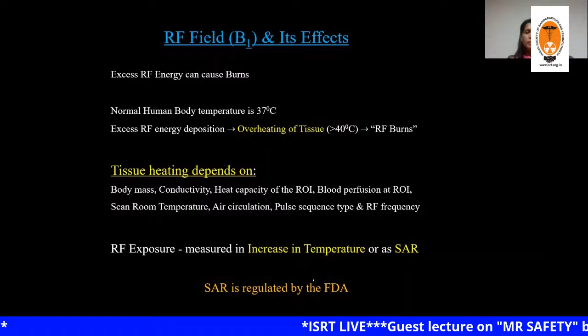To avoid any radiation-related injury to the patient, the system is provided with different operating modes. Once we choose to start scanning in the normal operating mode, the maximum energy deposited will be 2 watt per kg, and the system will automatically terminate the examination if the body temperature rises by 0.5 degrees centigrade.